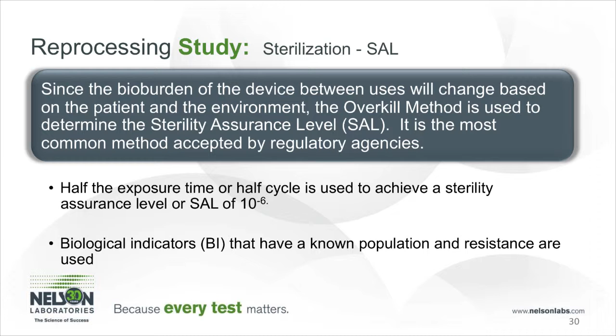Biological indicators are placed in the worst case or the most difficult to sterilize locations, and these include lumens, mated surfaces, and cannulas. When we do sterilization validations on a large tray of, say, for example, a hip implant, we may test up to 15 sites or even more in this whole tray to ensure that we are getting all the most difficult to sterilize locations, because we want to ensure that the whole tray is sterile coming out of the sterilizer.